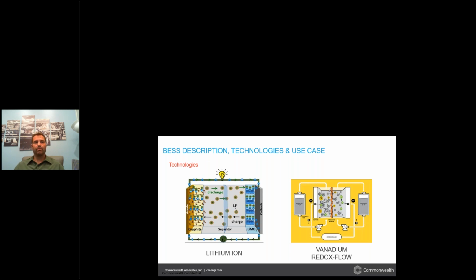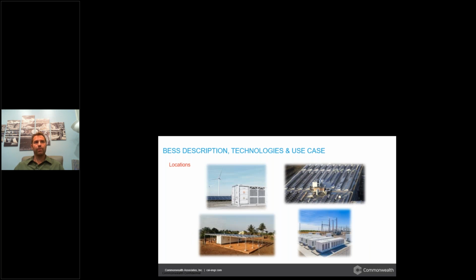Where can they go? Batteries can go anywhere. I'll mention some design considerations a little later, but the only real consideration is that they really should be as close as possible to the load. Top left has the battery co-located with wind and solar. This really could be anywhere. Top right has a system rooftop mounted. We just have to consider batteries are pretty heavy, so the rooftop needs to be reinforced, and there are also some NFPA 855 requirements to consider, and involving the authority having jurisdiction early is pretty key on a project like that.